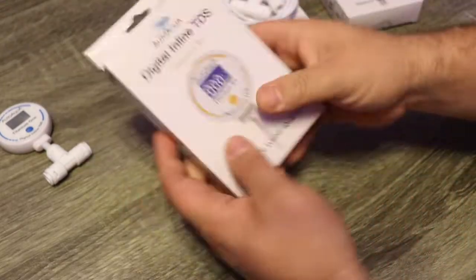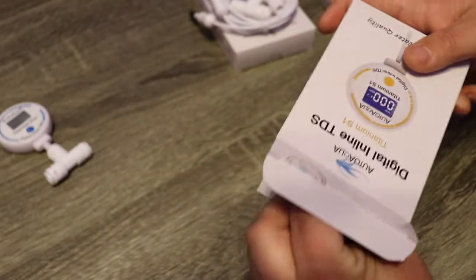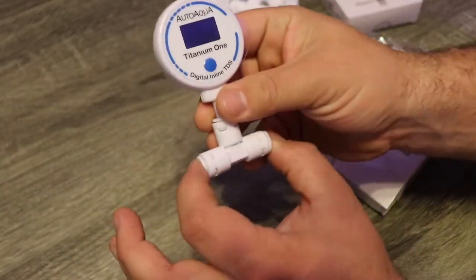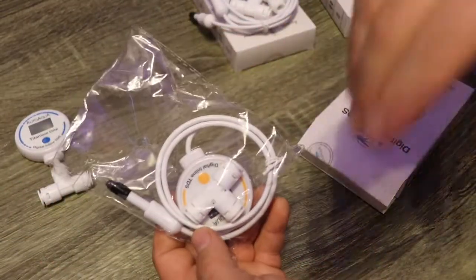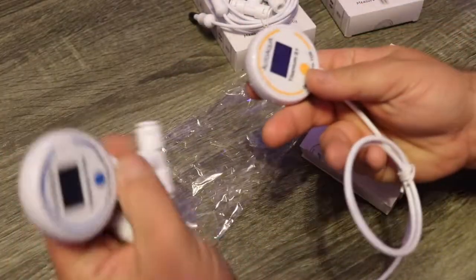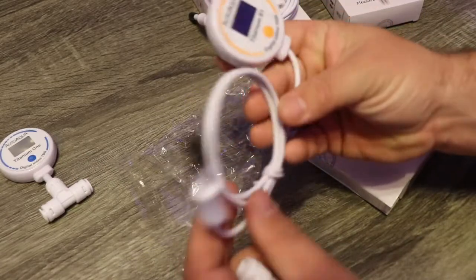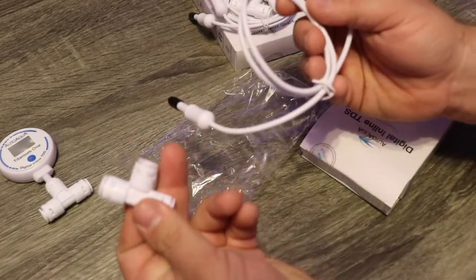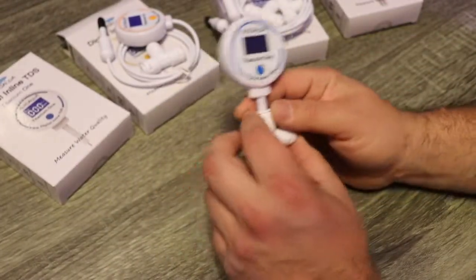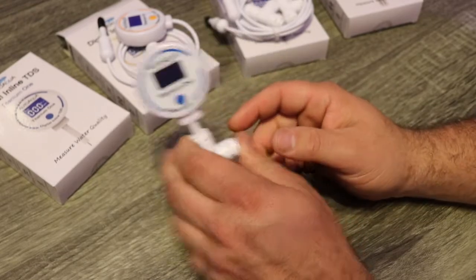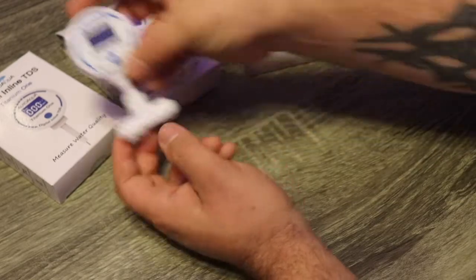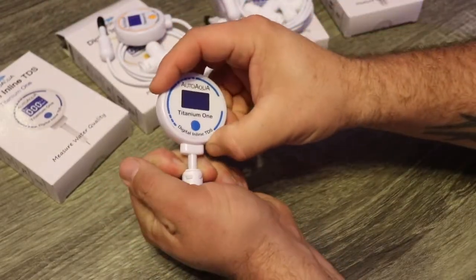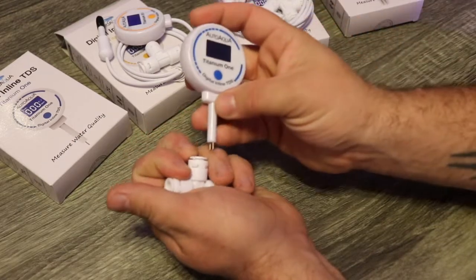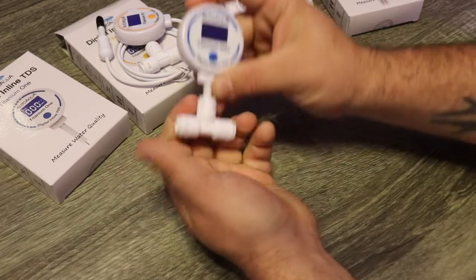The S1 is just like the titanium one, but it has the cord attached. So if it doesn't really work out for you to have the TDS meter right off the line, you want to put it in a position where you can situate it. The titanium one connects directly into your line, and you can put it on the infeed or outfeed of your RO filter, with the meter sitting right off the line. It's easy to take apart - you just pull the quick connect down, pull the probe out, and you can do a calibration or some maintenance on it. Easy to put back in place, you just push it down in.